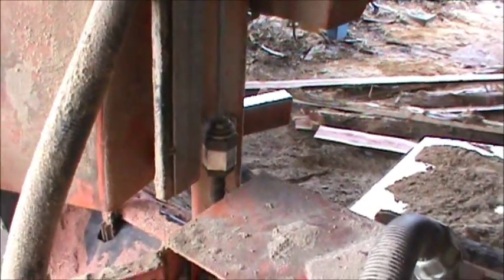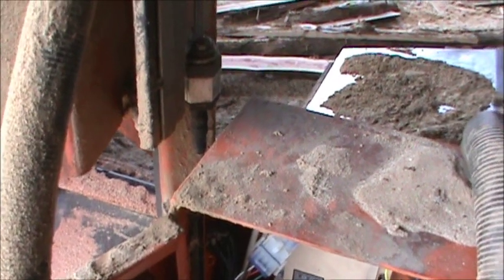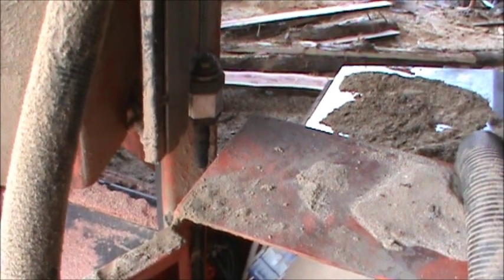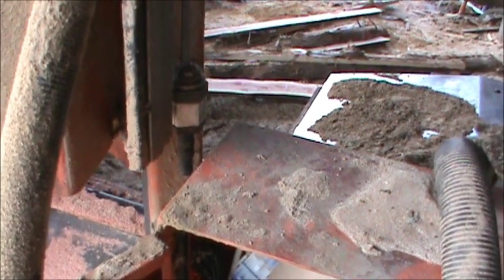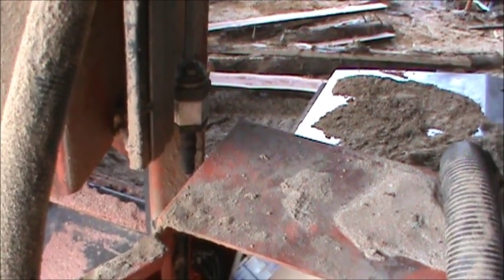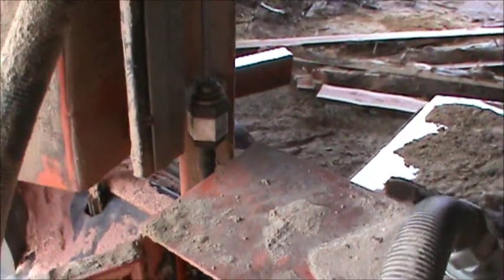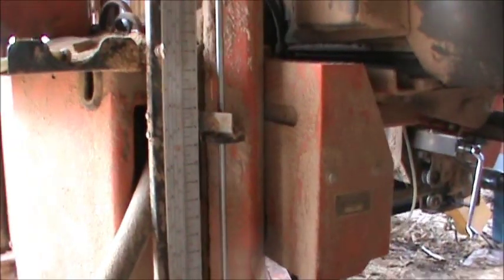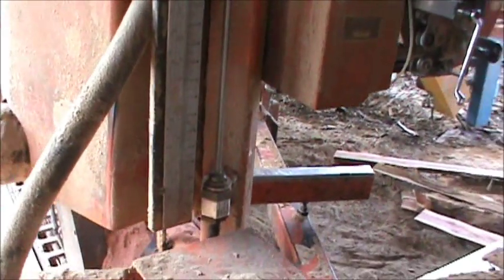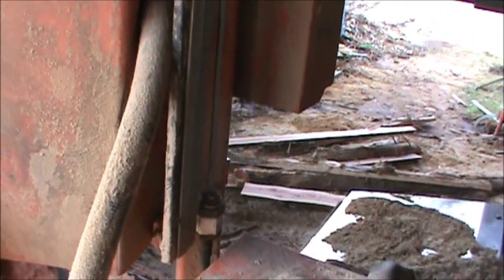There's a cable connection at the bottom of this transducer. You can kind of see the cable coming in there, and that needs to be kind of watched to make sure it's tight. If you have trouble with your Accu-Set and it won't know where it's at or where it's going, often it's the connection there to that transducer will get vibrated. It seems like once it gets tight enough and a good connection, it stays forever. There's a shield over top of this that kind of protects it. Other than that, it's a pretty dumb item but it is pretty expensive, so you need to kind of watch the cable that don't get cut or smashed or anything.